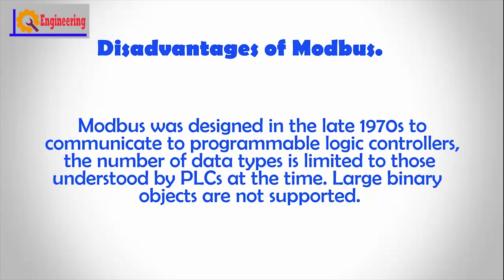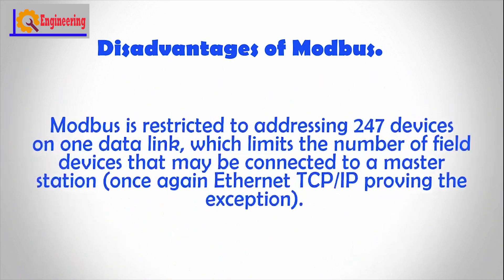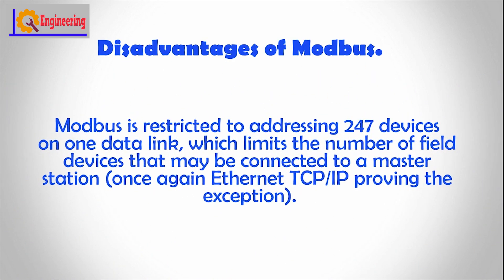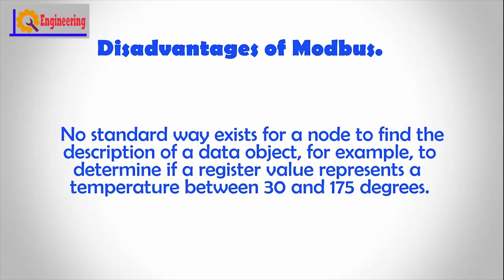Disadvantages of Modbus: Modbus was designed in the late 1970s to communicate with programmable logic controllers. The number of data types is limited to those understood by PLCs at the time. Large binary objects are not supported. Modbus is restricted in addressing devices on the data link, which limits the number of field devices that may be connected to a master station — with Ethernet TCP/IP proving the exception. No standard way exists for a node to find the description of a data object, for example to determine if a register value represents a temperature between 30 and 175 degrees.